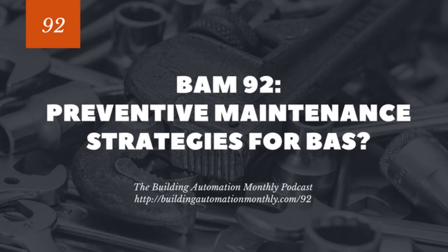But you don't hear folks talk about alarm tuning. And how often is this the case? You get a specification to implement a BAS at a new building, and it just says set the alarm to 55-85. That's it. They don't differentiate for occupied or unoccupied modes or whatever, it's just a broad number.